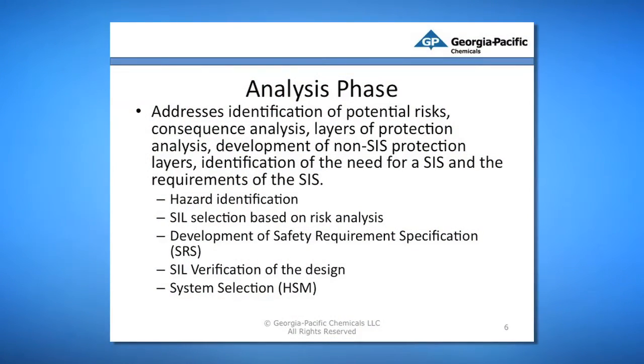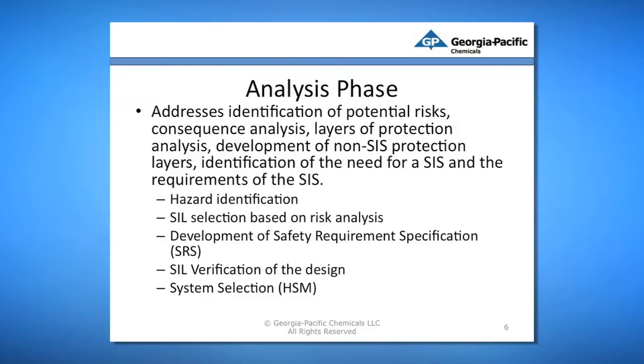In other words, you identify the hazards, you select the SIL, safety integrity level, based on the risk analysis. You can use different methods of coming to that, LOPA or other methods. You develop the safety requirement specification, SRS, and verify the SIL level of the proposed design. And then at this phase, in many cases, you also make the selection of your logic solver and other parts of your safety instrumented system.